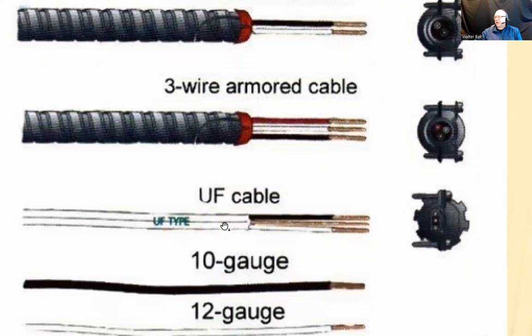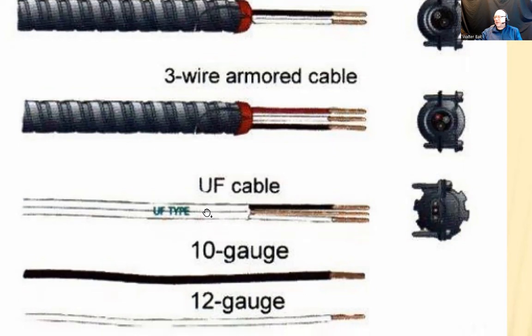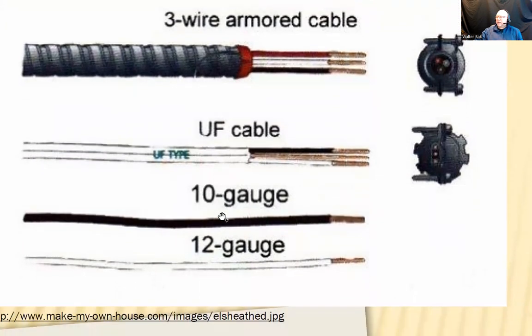All right. UF cable. When you see the UF, that means it's an underground feeder cable, which means it could be installed underground. Sometimes you're going to see a little designation that says B UF, for example, then that means it could be installed as a direct burial, which means you don't need any additional structures to support that. You can just put that in the ground as it is on its own, and it's rated for that.